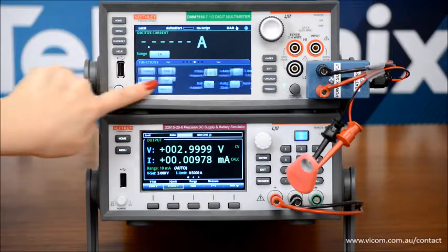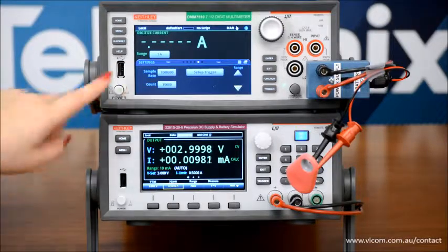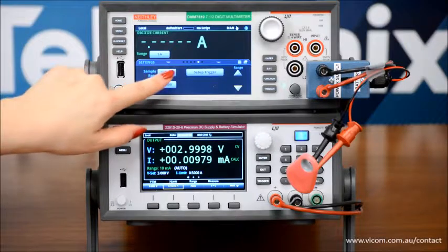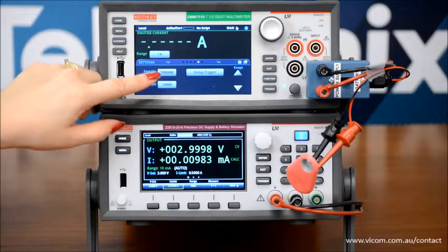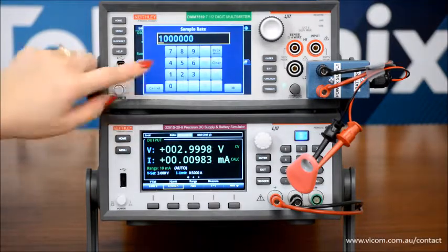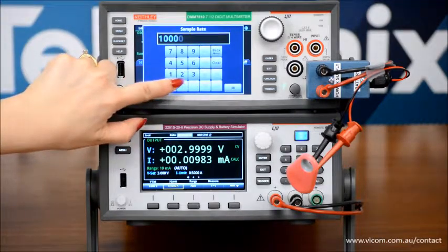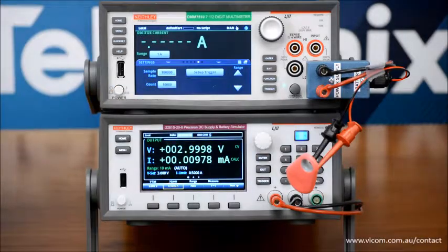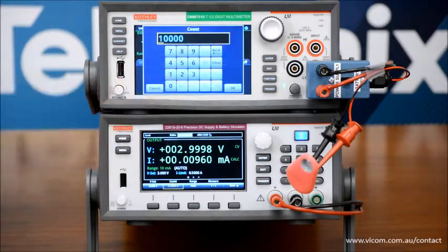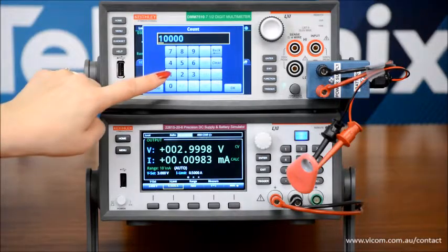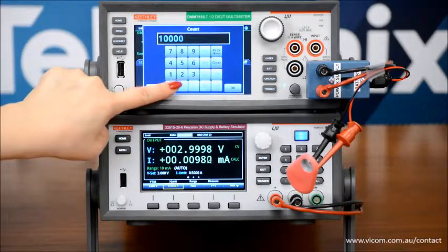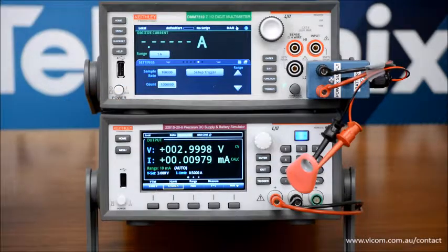Swipe the screen on the bottom. Change the sample rate from 1 megasamples per second, which is the maximum this DMM can do, to 100K. And change the count to 1 million to match the buffer capacity that we just set. So with 1 million readings, that's 10 seconds of data at 100 kilosamples per second, or 10 microseconds per sample.